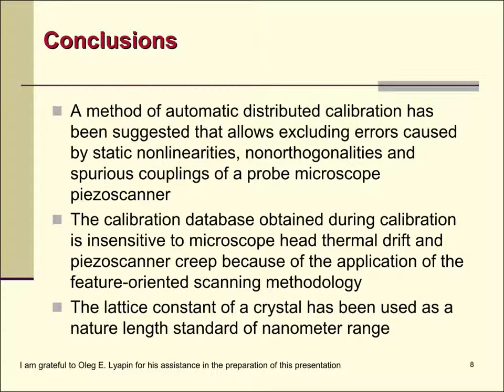Conclusions. A method of automatic distributed calibration has been suggested that allows excluding errors caused by static nonlinearities, non-orthogonalities, and spurious couplings of a probe microscope piezo scanner.